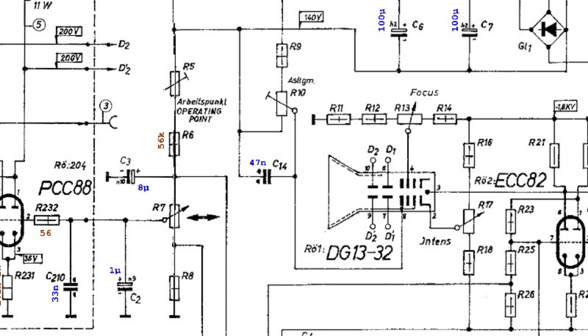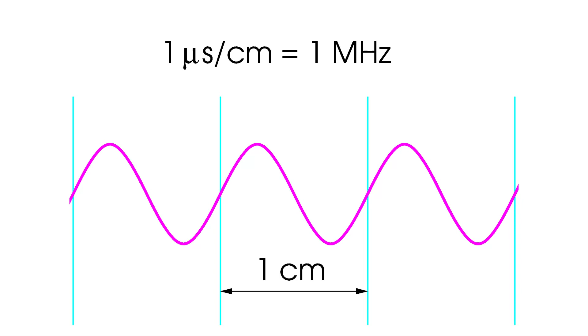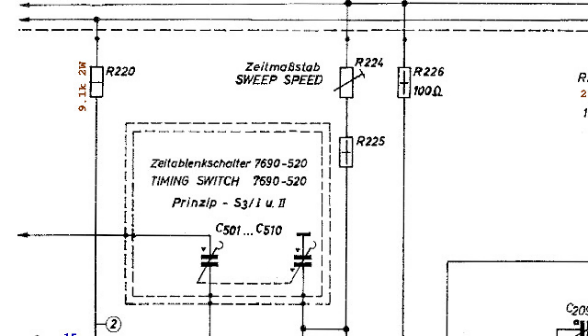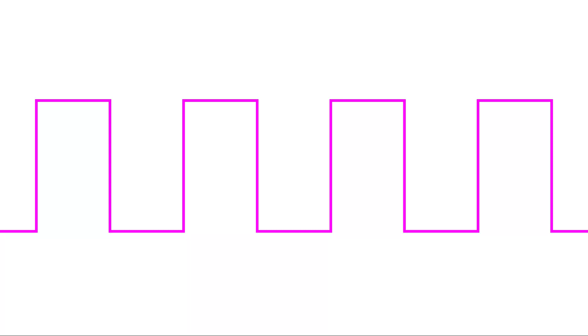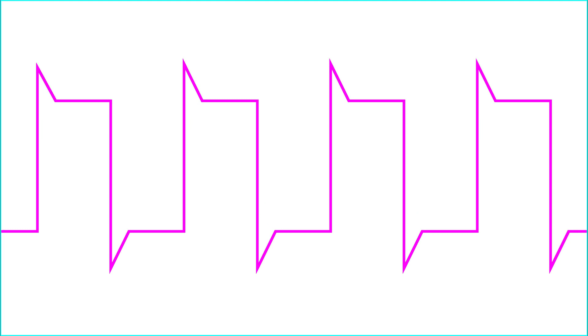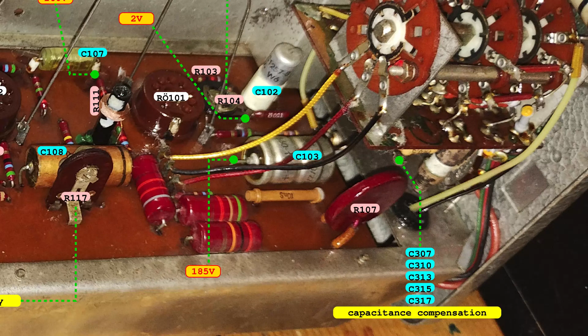Horizontal calibration. It is possible to calibrate the horizontal gain so that horizontally each centimeter on the CRT screen corresponds to the time selected. So, for example, selecting 1 millisecond per centimeter, each centimeter should contain the width of a cycle of 1 kilohertz. Similarly, selecting 1 microsecond per centimeter, a full cycle of 1 megahertz should be displayed on the width of 1 centimeter. The calibration could be obtained using a reliable function generator and adjusting the trimmer resistor R224. Capacitance compensation. If a square wave visualized with a selected vertical attenuation appears on the screen rounded or with an initial spike, it is probably necessary to adjust the trimmer capacitors C307, C310, C313, C315, and C317 to obtain a proper representation.